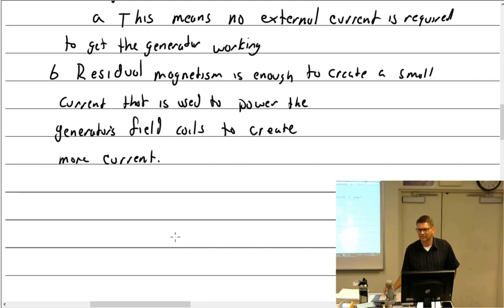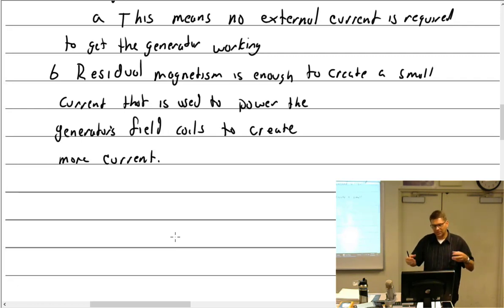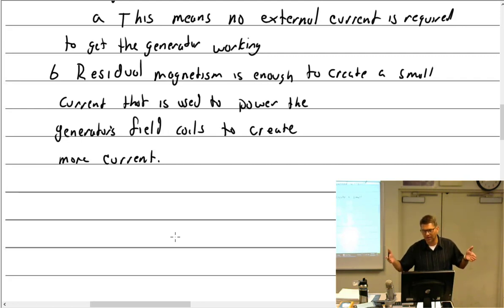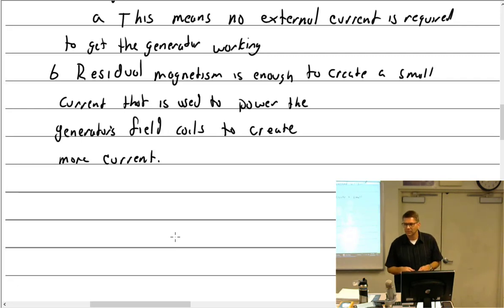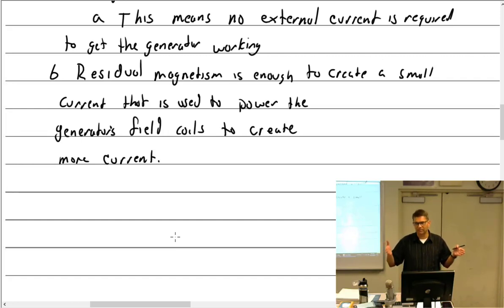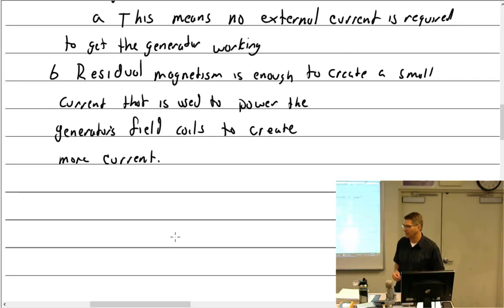The generator core has laminations of soft iron with windings, and a steel shaft. The field coils have a higher retentivity — they hold residual magnetism. The armature has low retentivity because you don't want it to retain magnetism since it's constantly changing polarity.